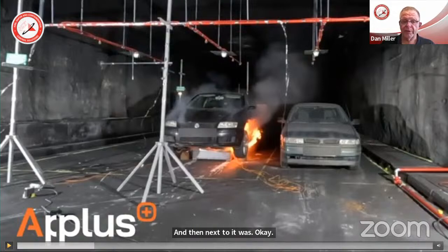They allowed a pre-burn time, letting the fire get going very well and really hot, well into thermal runaway, and then kicked on the deluge system. The deluge system involved several heads with F-500.